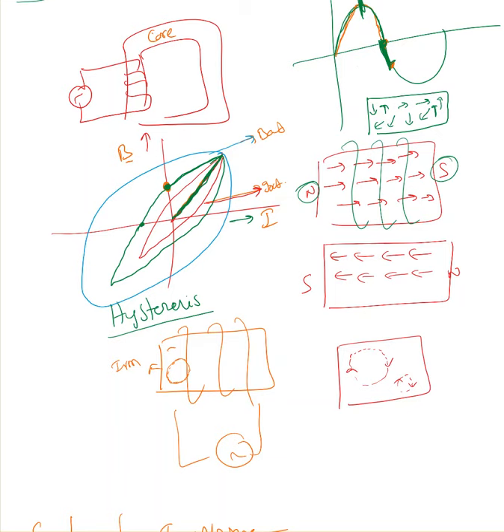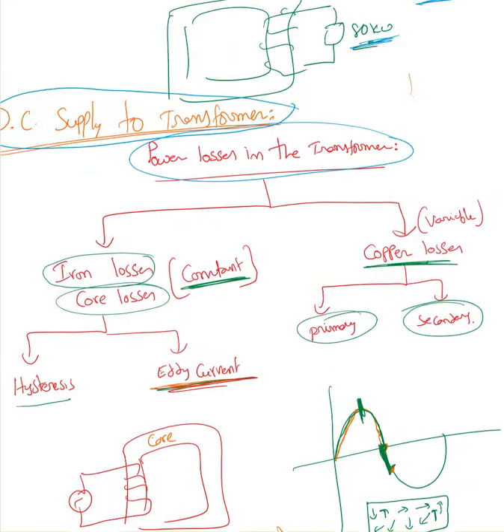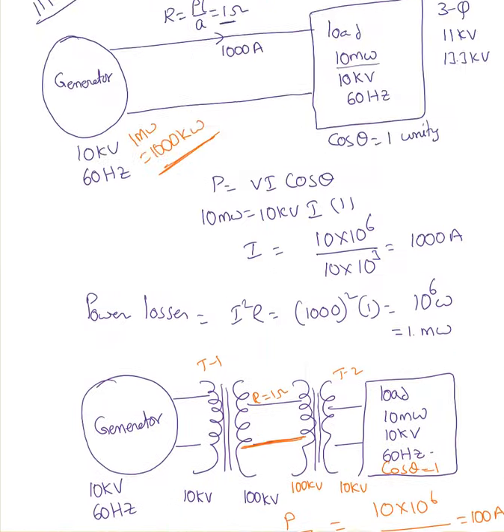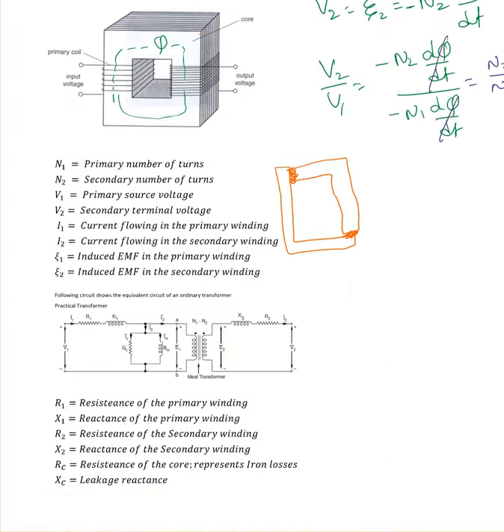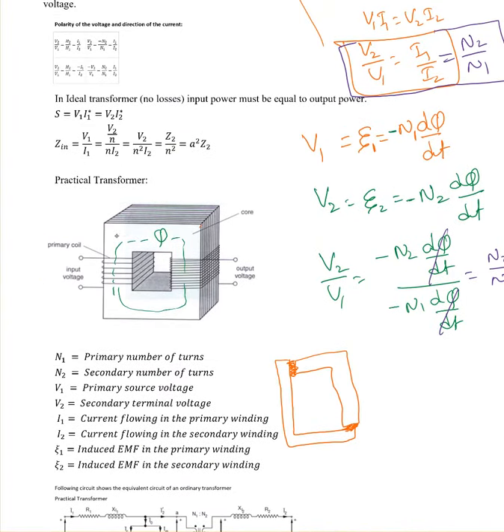How do we minimize these eddy current losses? They are minimized by slicing the core. If you look at this, the core is sliced with insulation between each slice, so the core resistance increases and induced currents are reduced.